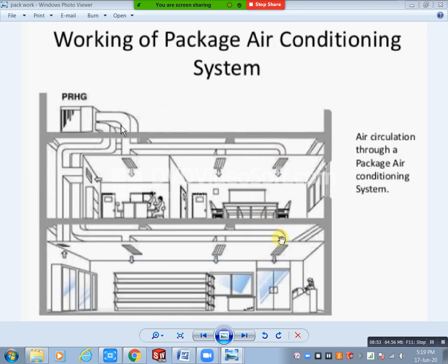At the same time here, this one is wall mounted. Okay, return air. Just observe this one. This is the return air duct. For example, here we are getting total return air, right? But we need to extract some air, 30% of the air. As a thumb rule, we need to extract 30% of the air, and at the same time we need the same amount of fresh air also. For example, for fresh air purpose we need to give an opening here. You can zoom this one.